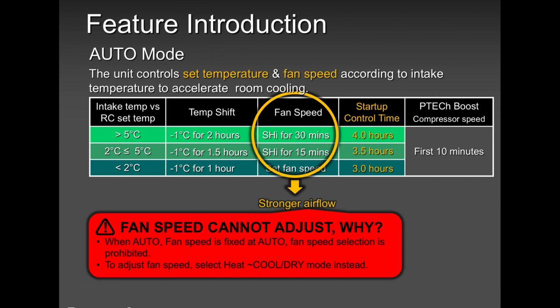It will fully open. And if you want to test it, go manual. Or if you're not sure of how to go manual with the louver and the fan speed, run it in cool mode. Even if it's very cold outside, just for a few minutes, run it in cool mode to make sure that the fan is running well, all the speeds are working, the louver is opening up and down, left to right, and the speed changes. The fan speed changes.